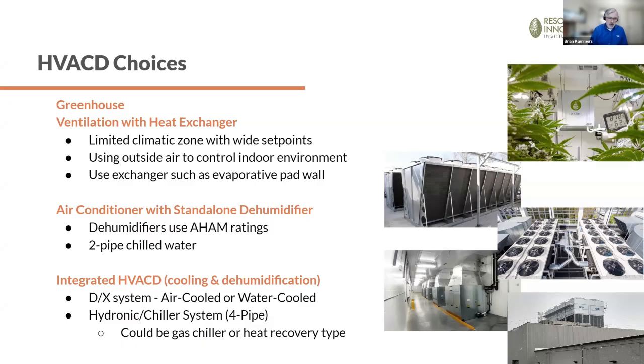But the standalone dehumidifiers also put heat back into the room as part of the refrigeration process, which that comfort cooling air conditioner has to take care of. And then there's 2-pipe chilled water systems to cool these rooms down. And at the top end, the one where you're controlling everything, the integrated HVAC-D, it has cooling and dehumidification. Here you see that nomenclature DX standing for direct expansion, just like at your house.